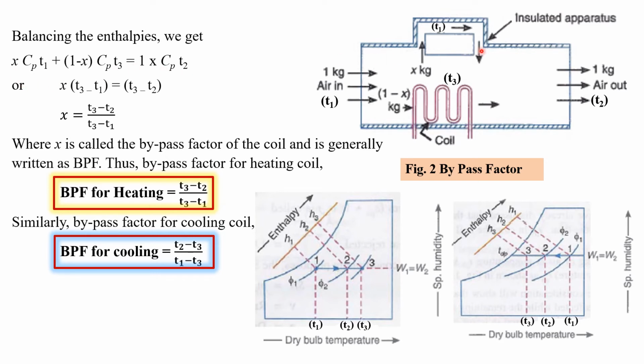So this is obviously x into Cp into T1. This is for the first air stream, its enthalpy. For the second air stream, which is flowing over the heating or cooling coil and getting its temperature changed from T1 to T3, it is (1 minus x) kg, basically the quantity or mass flow rate, multiplied by Cp into T3. And finally at the outlet we have 1 kg Cp into T2. So from here we determine the value of x as (T3 minus T2) divided by (T3 minus T1), that is, the temperature of the heating or cooling coil minus the temperature of air at the exit, divided by the temperature of the heating or cooling coil minus the temperature at the inlet.